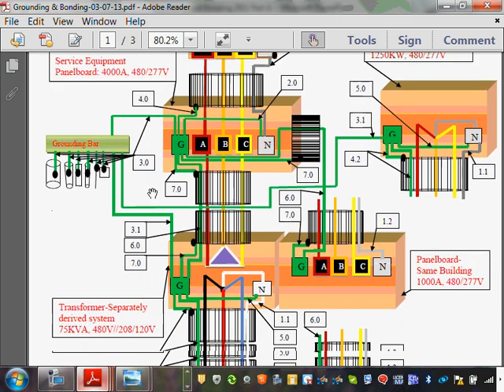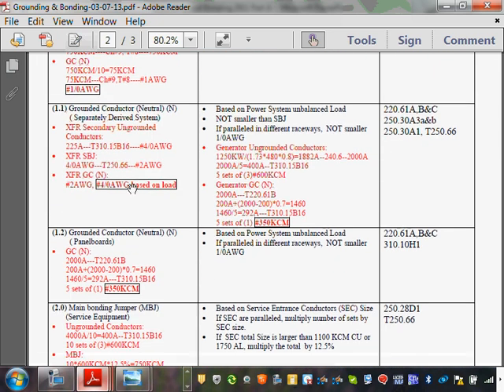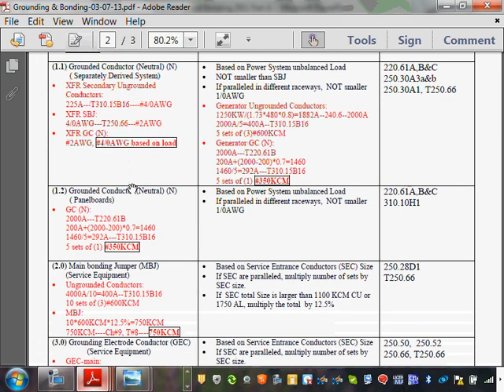So for the main bonding jumper, if you guys go to 2.0, I'm going to go down into 2.0. It's called main bonding jumper. When it comes to grounding and bonding, guys, terminology is everything. It's not enough to say bonding jumper. If you say bonding jumper, it's meaningless. Is it main bonding jumper? Is it system bonding jumper? Is it supply side bonding jumper? Or is it equipment bonding jumper on the load side? So there's 4 bonding jumpers. So when you say bonding jumper, it's meaningless.